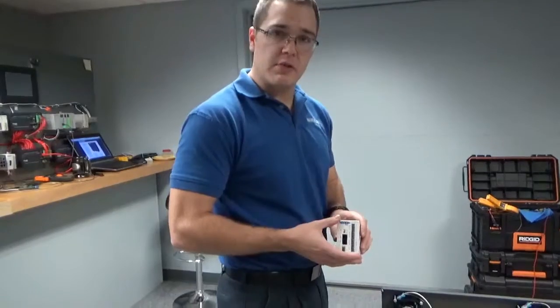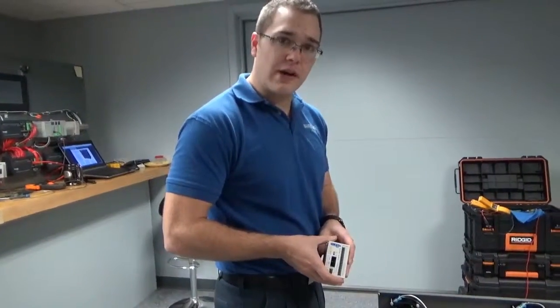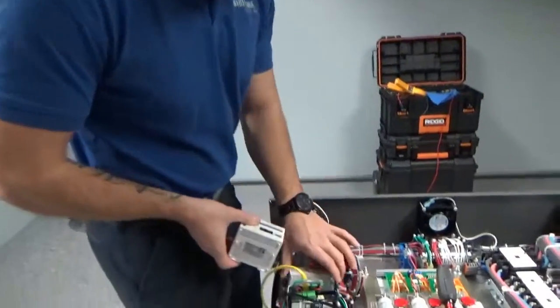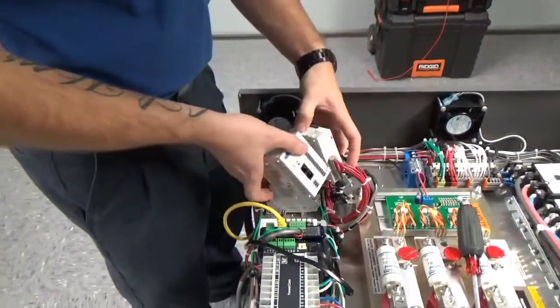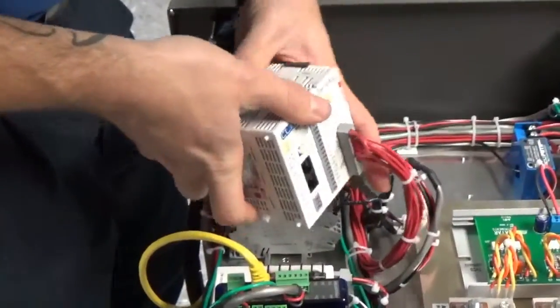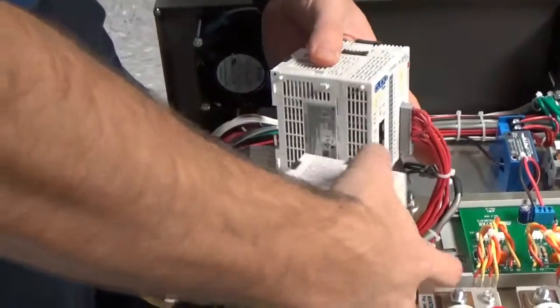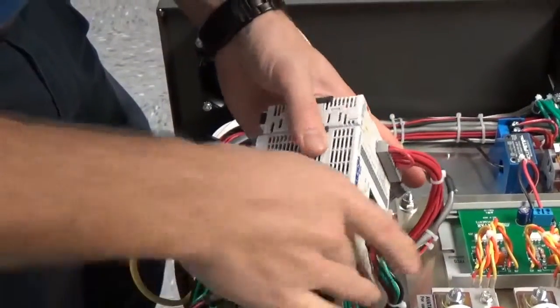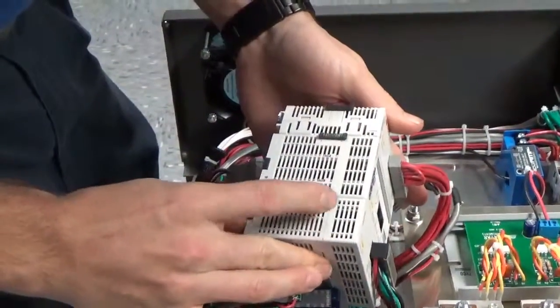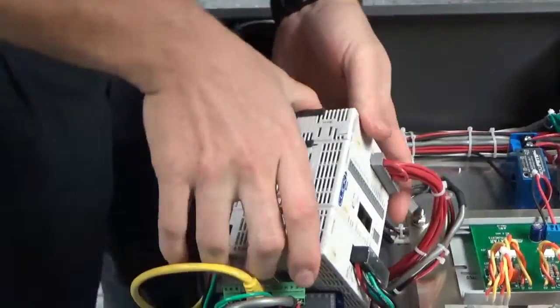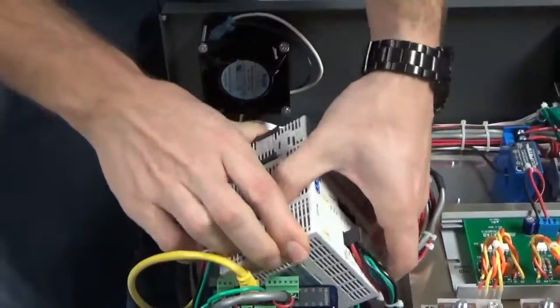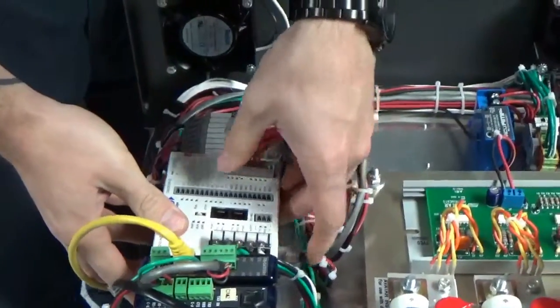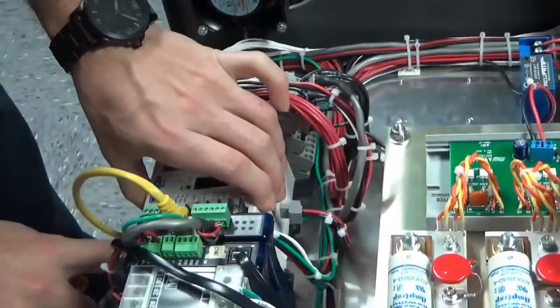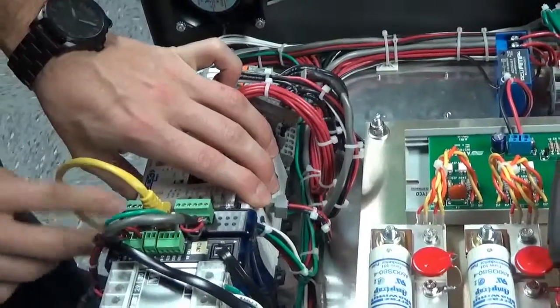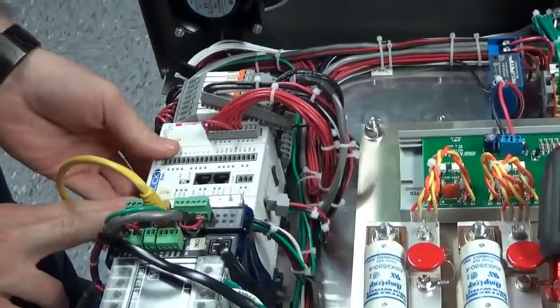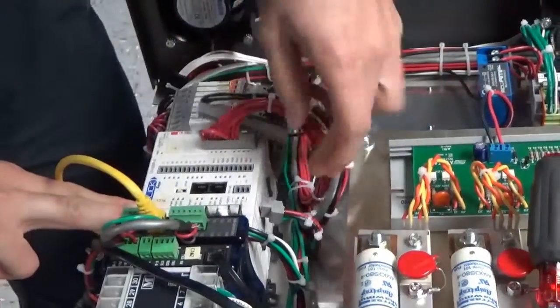Once we have our replacement PLC, we're ready to install it back into our load bank. First, just by sandwiching our power supply, our PLC, and the output module together. Once they're all together, we're going to lock them in. 2 tabs on the top. This one's going to have 2 tabs on the bottom. Once they're locked into place, at an angle, you're going to set it above the DIN rail and slide it in and tilt it straight.